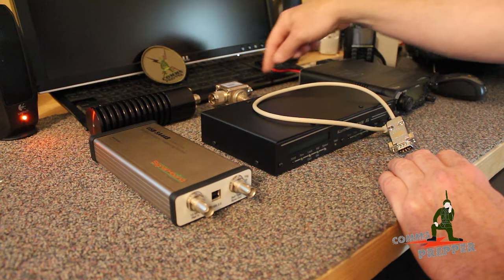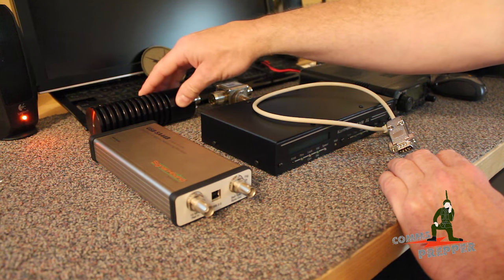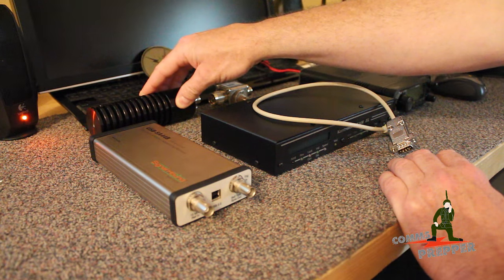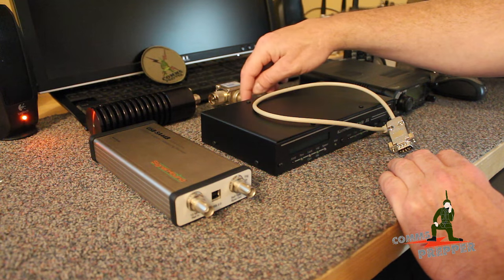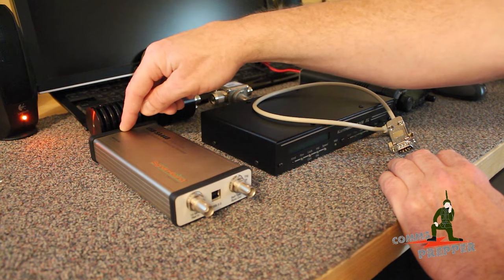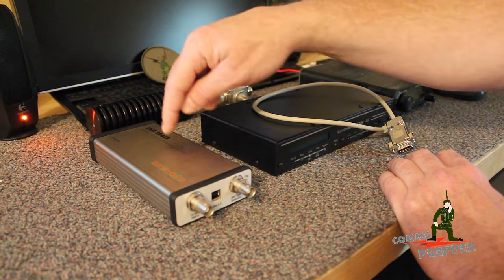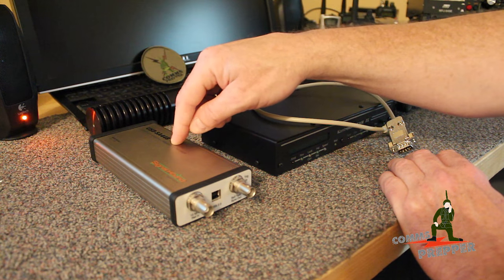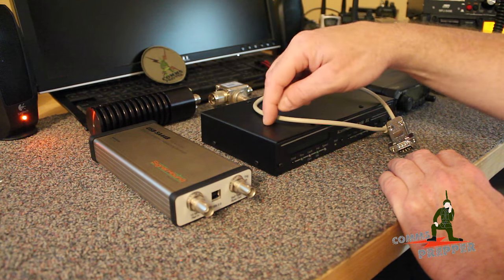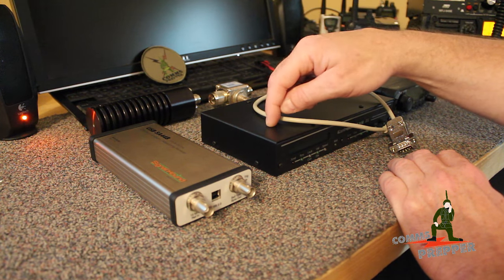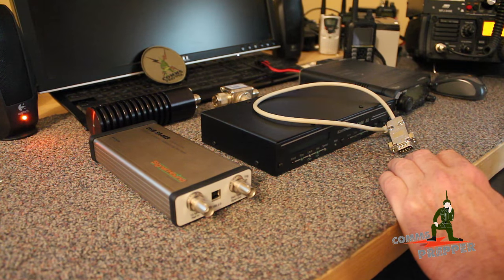So we're going to come out with 10 watts, come to the RF sampler. Majority of that energy is going to be absorbed by the dummy load. We're going to get a small sample out of the RF sampler to bring into the spectrum analyzer. With its companion Spike software, we'll be able to look at the deviation level once we put this in the calibration mode with Hyperterminal. So what I'll do now is roll over to the desktop software. We'll get this all hooked up.